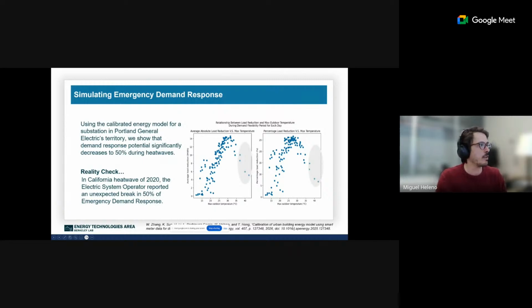We went back and looked at the California heat wave of 2020, and the system operator reported that they asked for 800 megawatts of emergency demand response, and only 50%, only 400 megawatts, actually responded. There's never been an actual validation of this, and we arrived at similar numbers here in Portland General Electric.